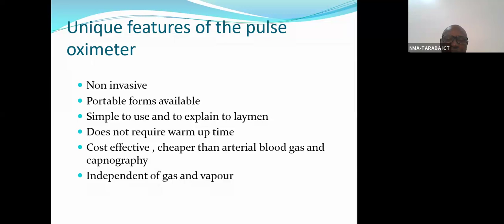It also has what we call tone modulation. This means the sound changes when the pulse oximeter reading is dropping; the tone begins to become harsh. In fact, if you get used to that tone, you can even estimate what the reading is. It has been a source of help to anesthetists and others that use it, because you have many things to do. You can't just sit there at the monitor. Even if you are far from the patient, if the reading starts dropping, the frequency and the tone start becoming harsh. So this can alert you from wherever you are to come and attend to the patient.